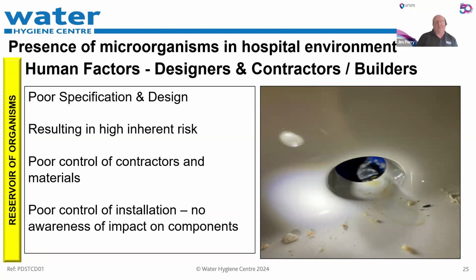So what do our designers and builders introduce? Clinical hospital hand wash basins being used as urinals during the build, where there's been no toilets or water on. We've actually seen hand wash basins being used as a urinal. You can see there in the photo, yellow staining and yellow droplets. That's resulted in quite a high risk for our commissioning of the water system. Components not kept in sealed bags or covered.